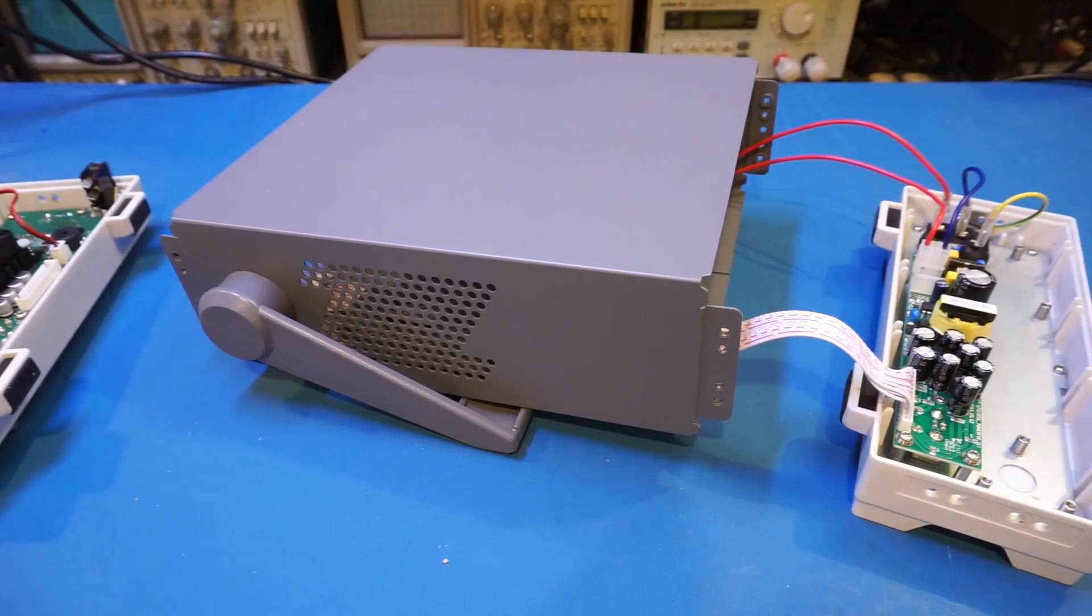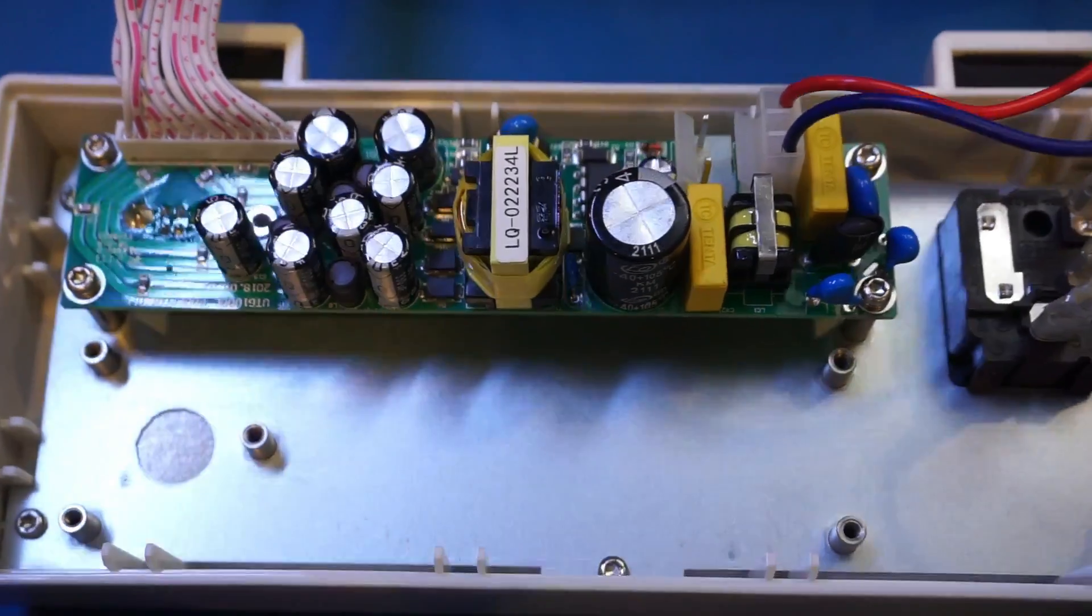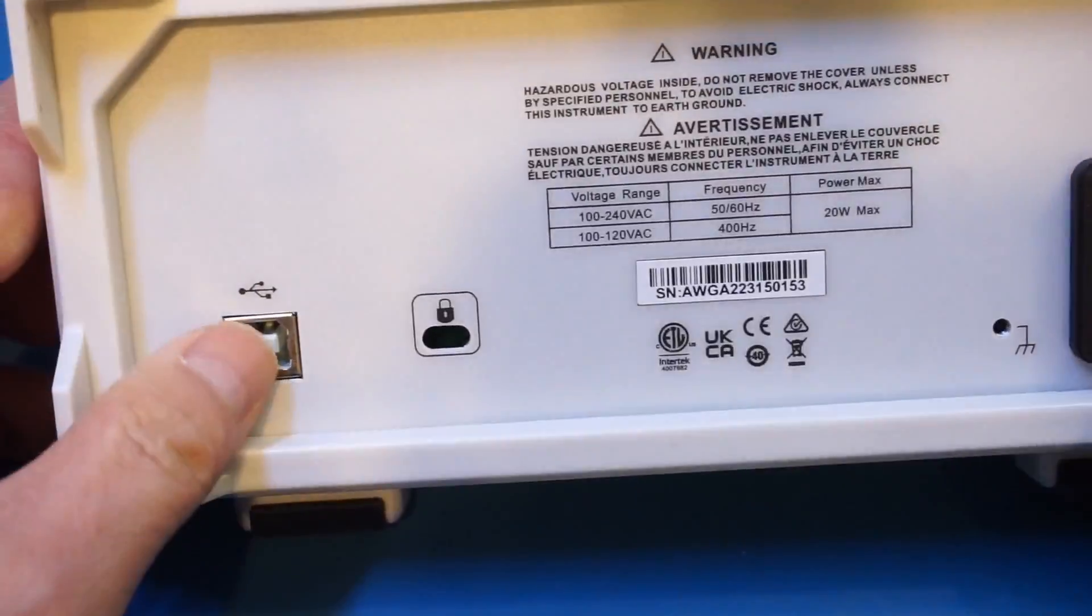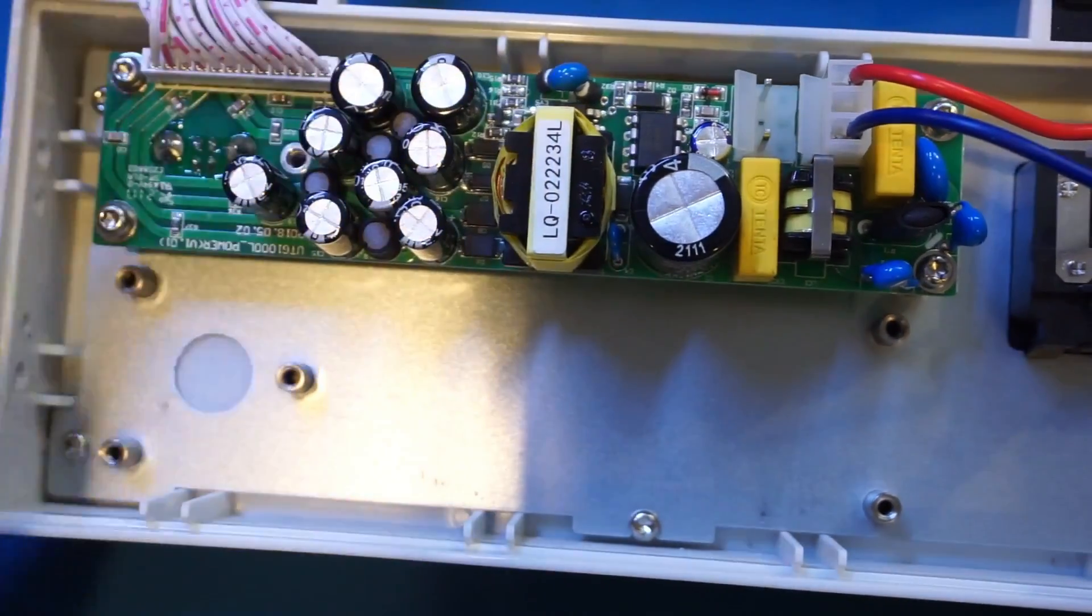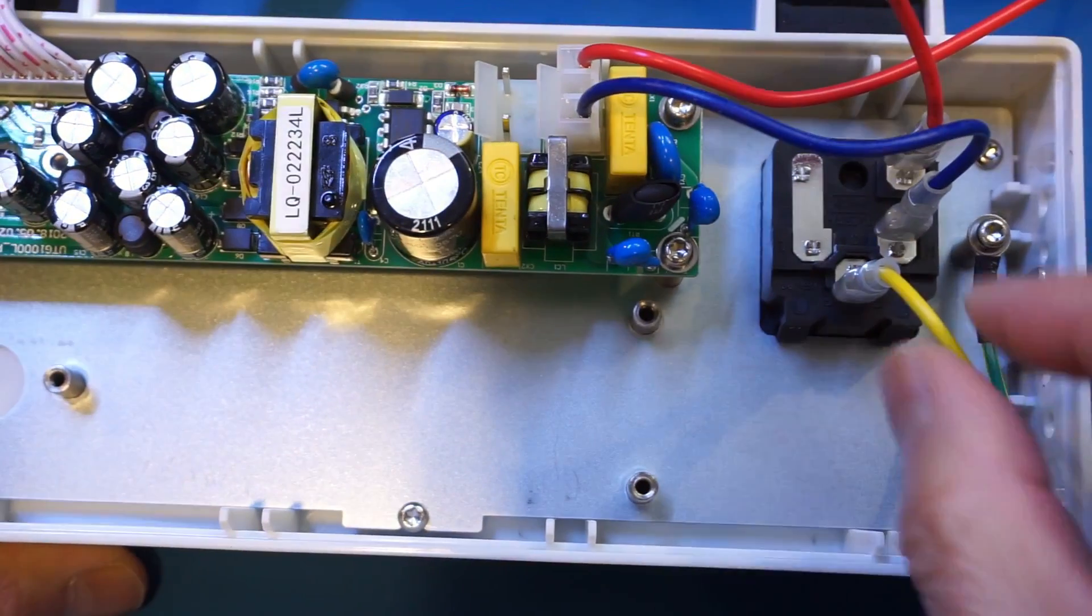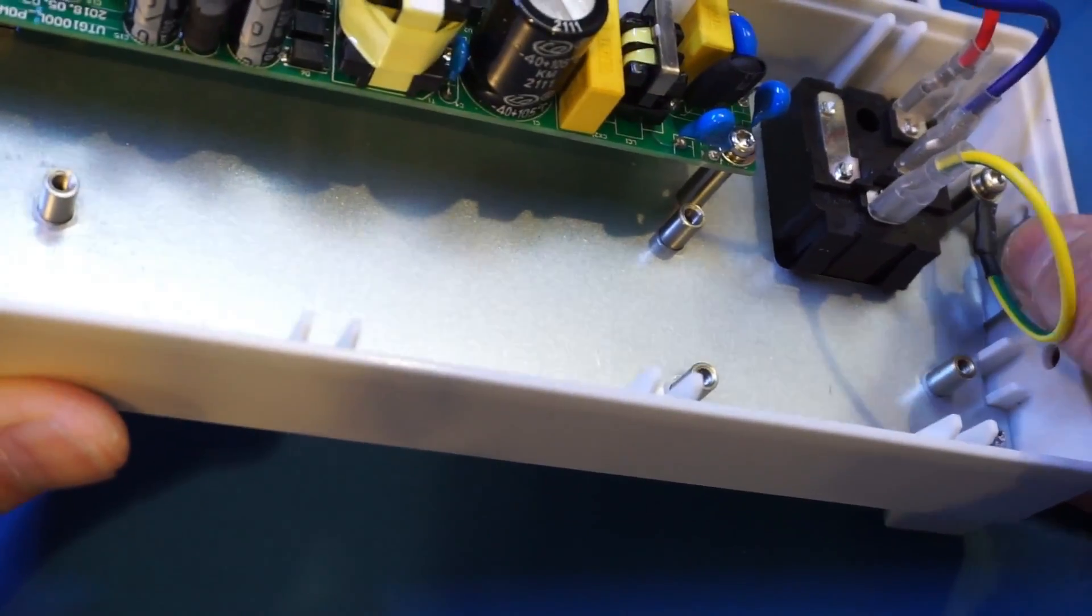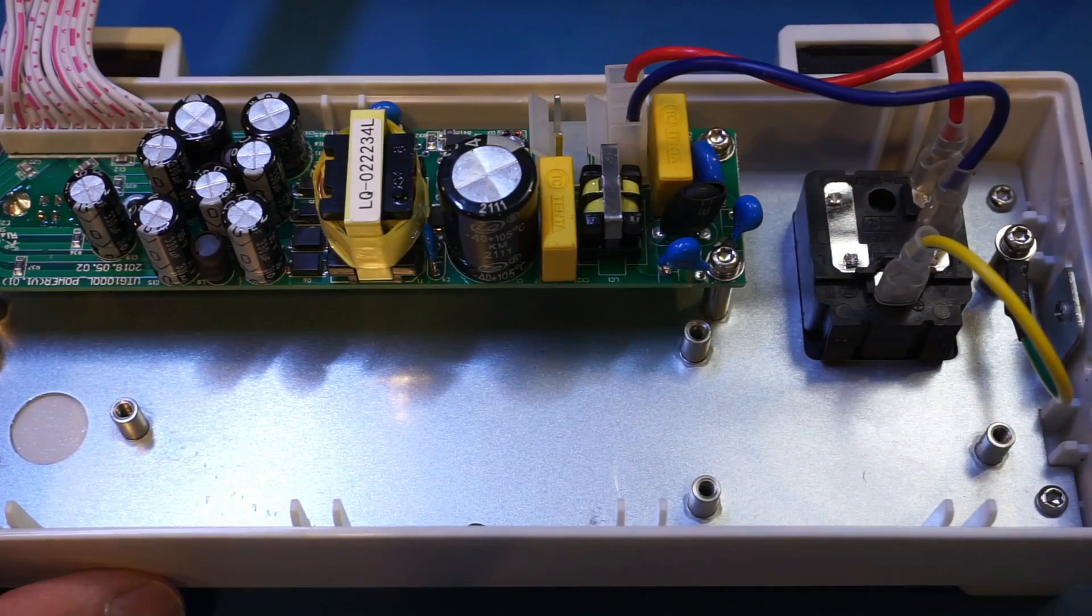All right, let's take a look at the power supply module first. By the look of here you can see we don't actually have a whole lot going on on this power module. Now it looks a little bit busy because we also have the USB port here and there is some additional circuitry to support that. If you look at the power supply here, you will see it is actually fairly well made. The earth ground is tied to the chassis and you can see we do have a separate tab. This one screws into the main case so the case essentially is tied to the earth ground.